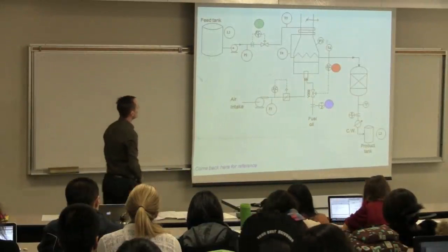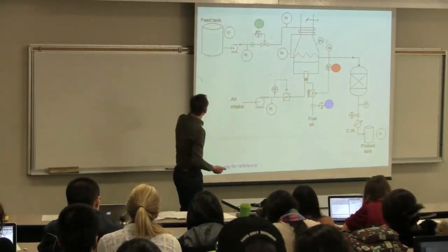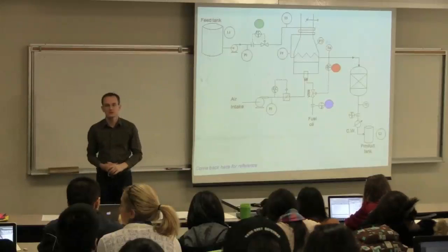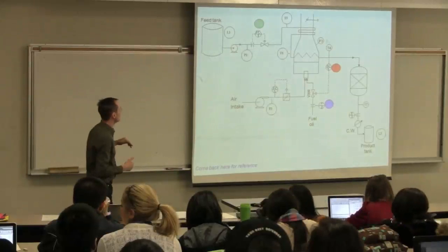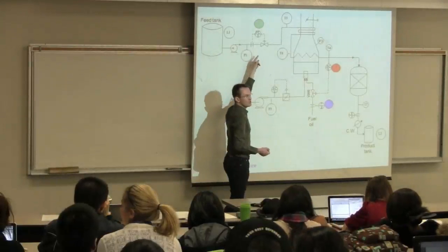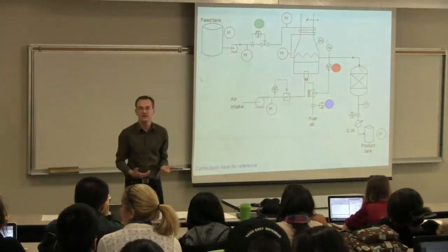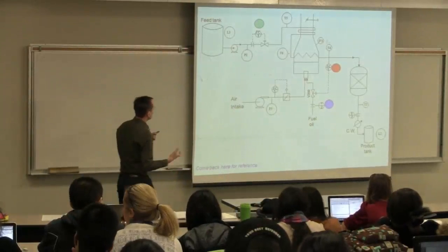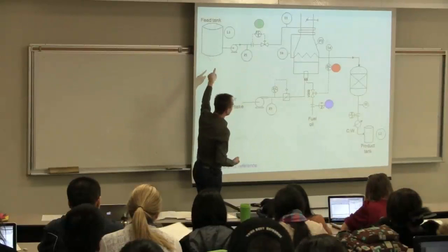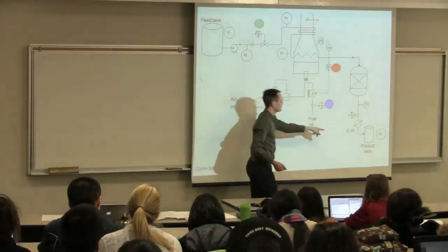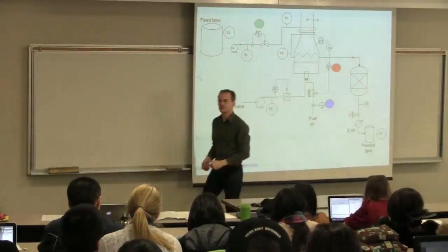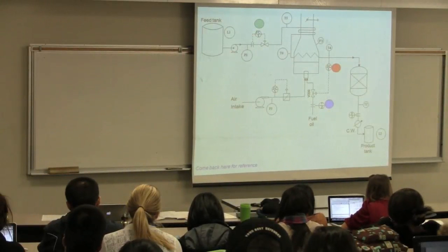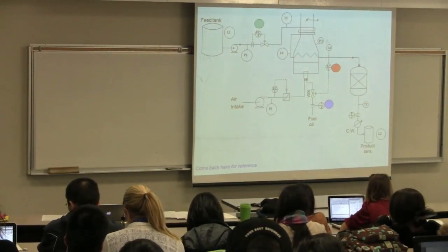Another one that you can check is to ask the expert system, this tank is a large storage tank, is the level L1 dropping? If level L1 is not dropping, but F1 is showing an increase in flow, there's an inconsistency there. Likely that flow meter is broken. So if L1 is dropping, F1 should be showing an increase in flow. Another consistency check is if L1 is dropping, L2 must be rising. So we've got several ways to ask the plant or the expert system to verify whether our sensors are working. So we're checking there for consistency.